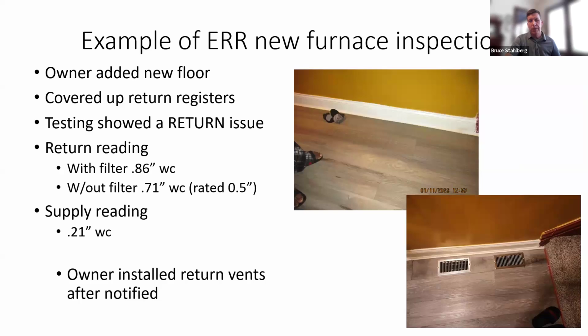One more example here. This was a publicly funded furnace. I went out to do the inspection, and I noticed that the return readings were very high. Without the filter, it was rated, that was 0.71, with the filter 0.86. Supply, not really a problem. So this was all on the return side.